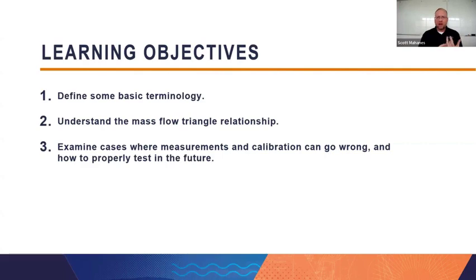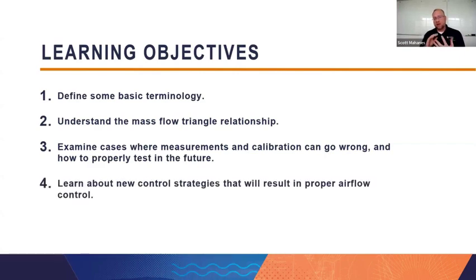If I have a calibrated airflow sensor that's perfectly calibrated for volume, I still have an issue with the way I control airflow. I've got to talk about how there needs to be a paradigm shift to controlling airflow not just by volume alone, but by mass. And at the end of this, hopefully I have time to share with you a simulation that shows how mass airflow numbers don't equal the way you set up air handlers to run. Oftentimes you end up with a large error, up to even 125%, as I think I'll show you in this example.